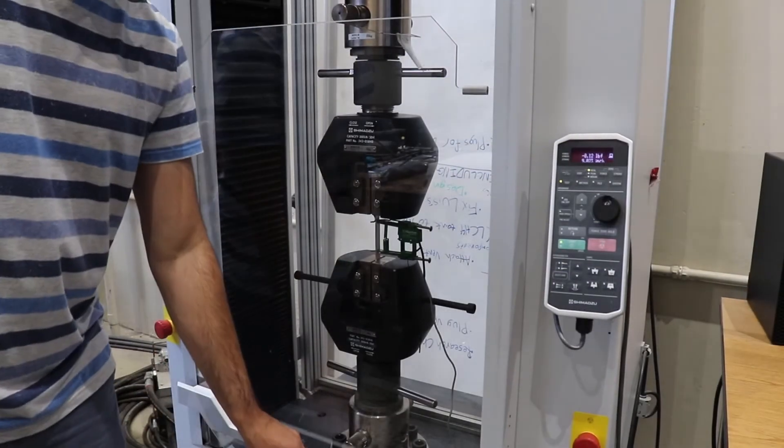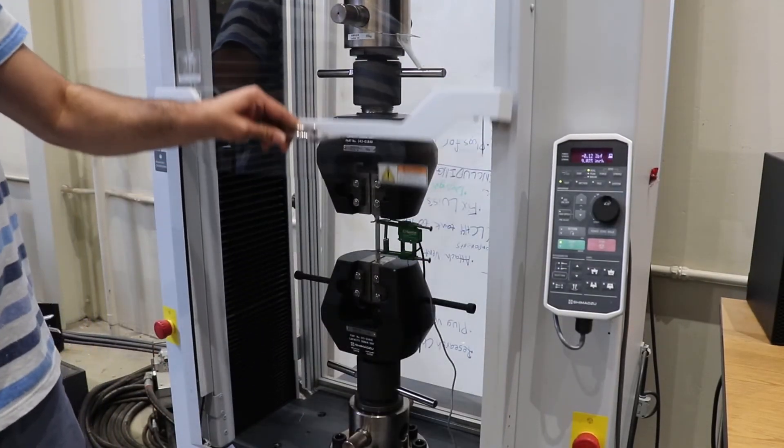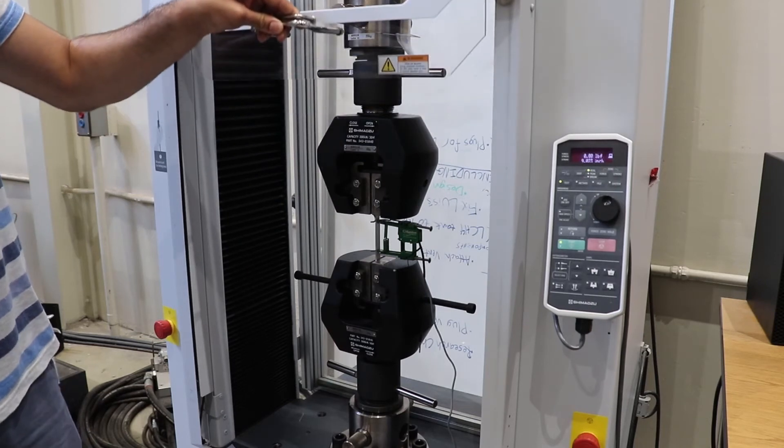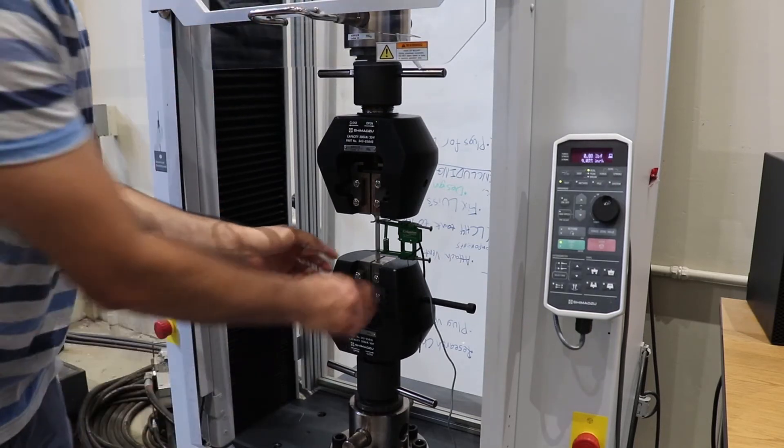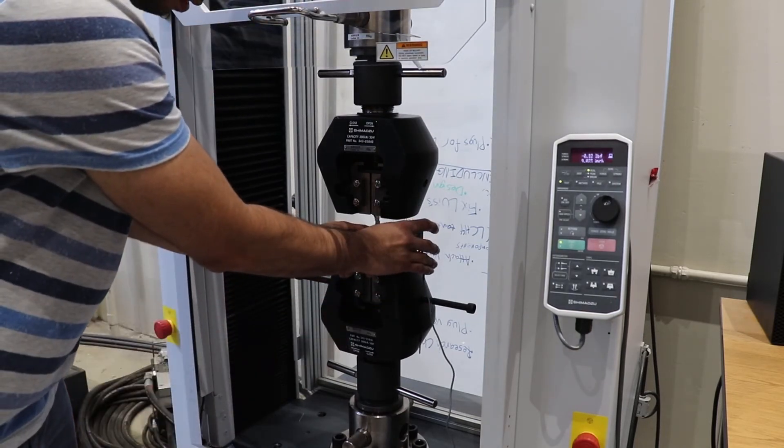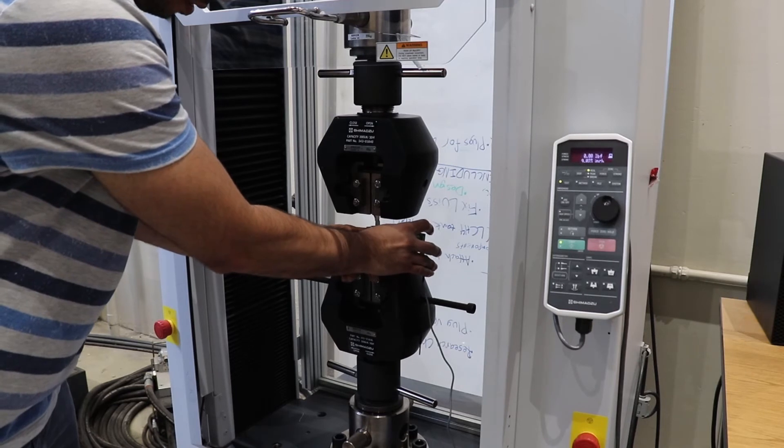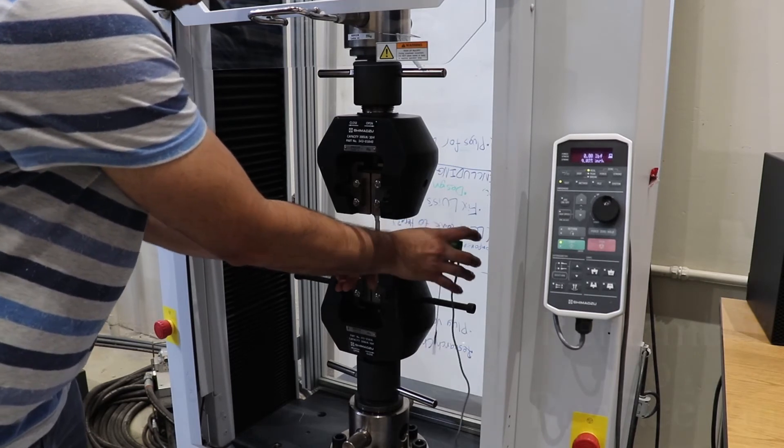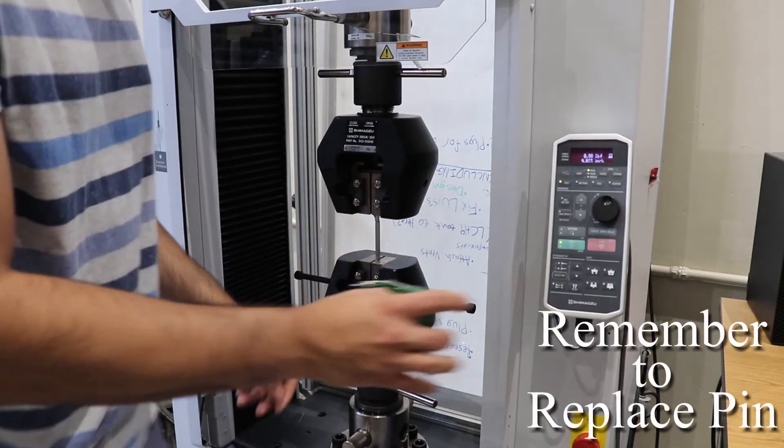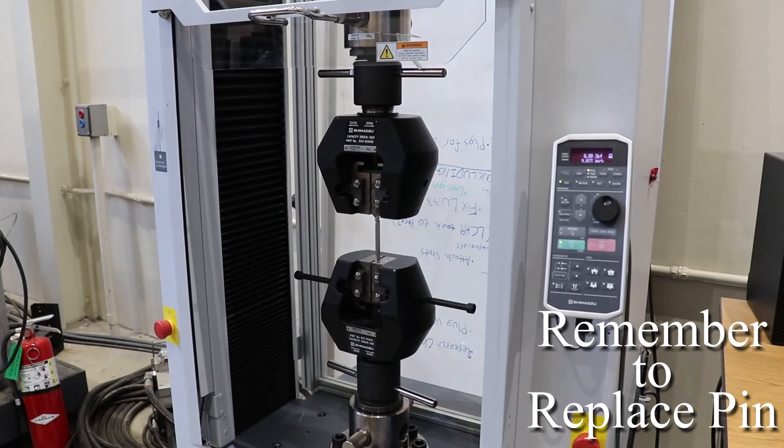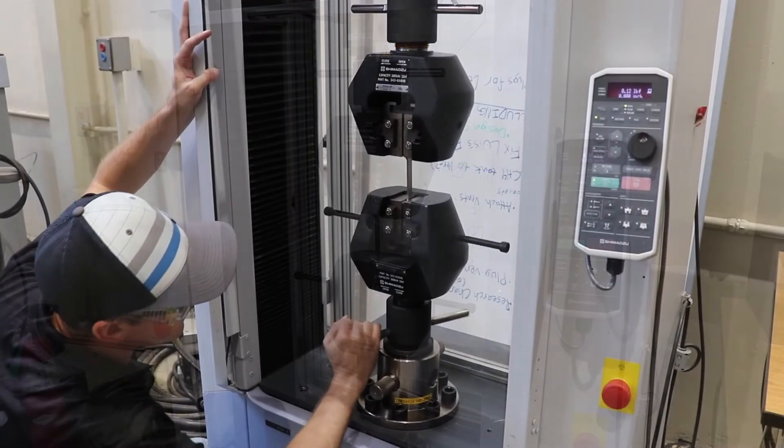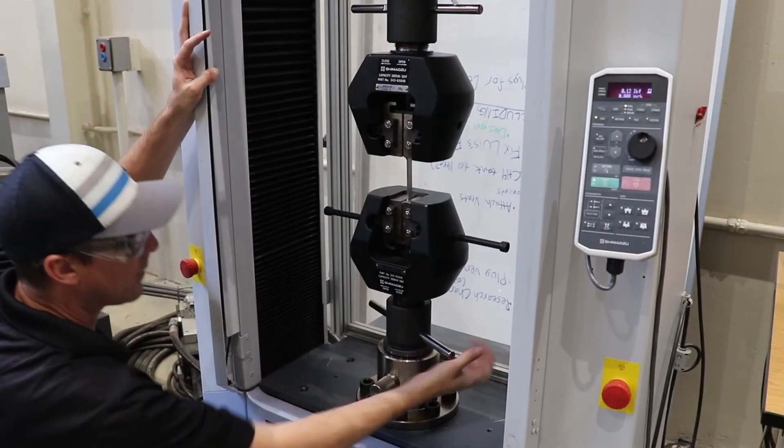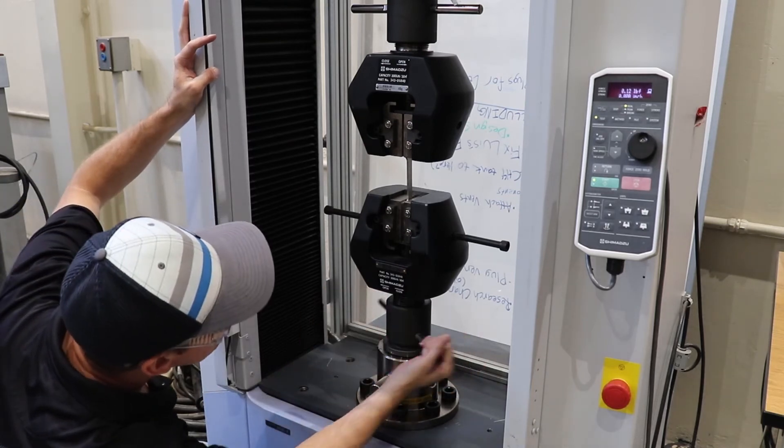We now begin the teardown process. First, we raise the shield. Next, we remove the extensometer being very careful as it does not have its pin in at the moment. Our next step involves untightening the jaws and removing our used specimen.